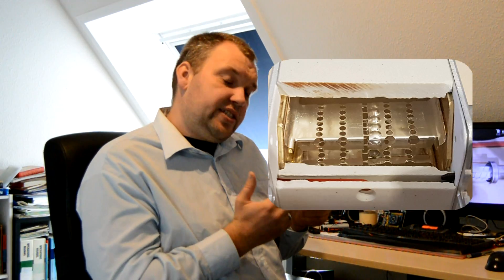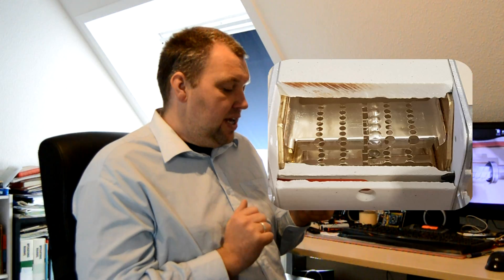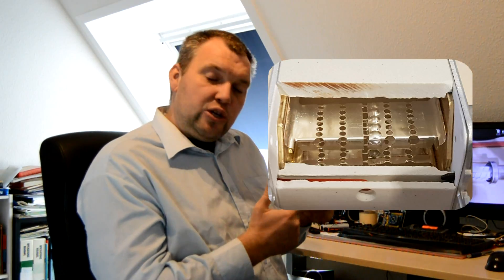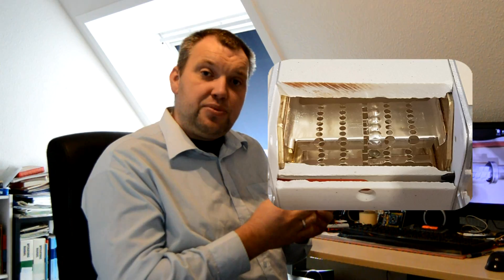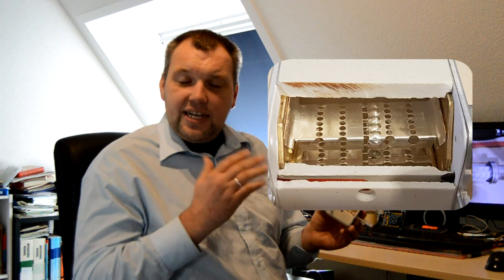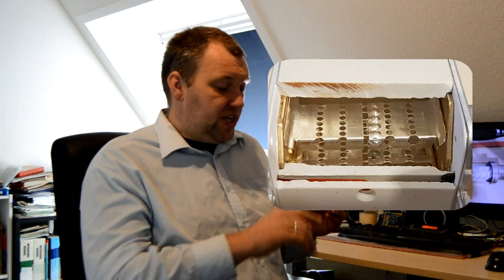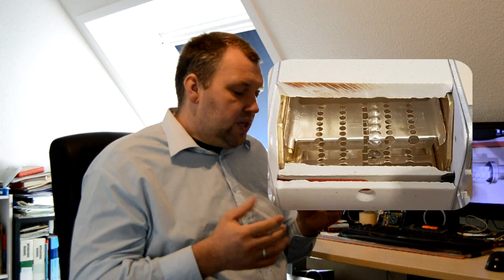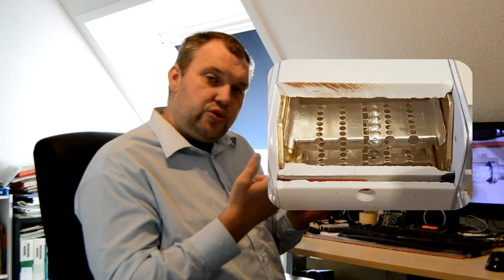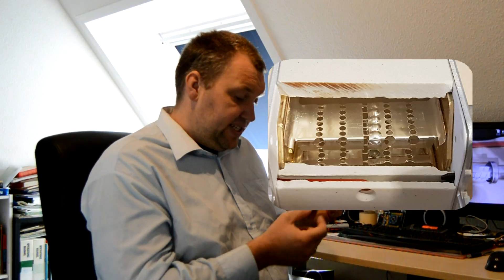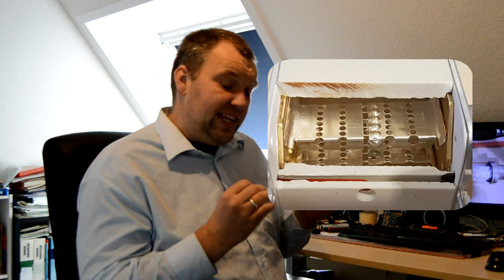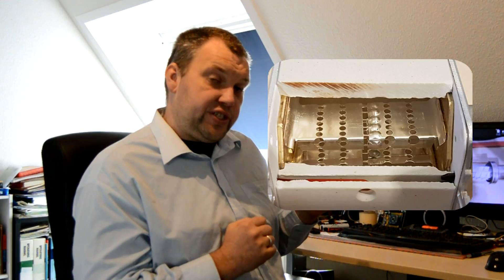So when we are going to exceed the temperature that this metal can handle, it's simply going to melt over these points. And when that happens usually an arc is generated and it will arc across instead, but the arc will generate even more heat so eventually it's going to the next set of holes on both sides, and if there's still an arc it will go through the third set.